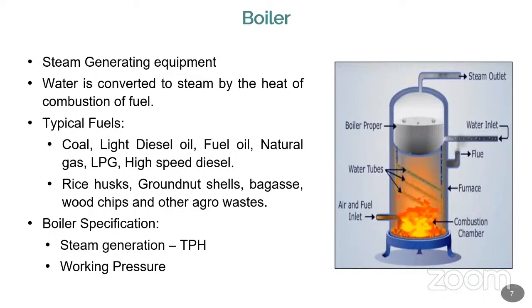I don't know whether you go to the canteen, mess area or kitchen area to see what type of boiler they have. Recently, I went to one college in Erode where they are using a 0.5 tonnage boiler to produce steam for cooking. In hostels, they use steam for cooking rice, boiling vegetables, water and milk. Most of the time it will be a 0.5 ton boiler. Sometimes it may be a 1 ton boiler.